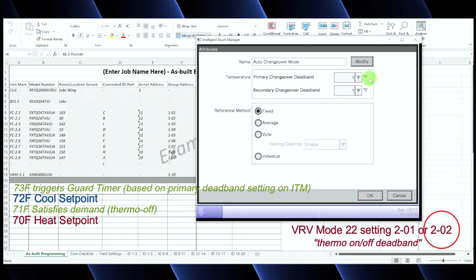You might have set it for 15. You might have left it at 60. I don't know. At any point in time, if the room temperature gets to this secondary deadband of 1 degree, so 74 degrees in our case, it will override the timer and immediately change over. I always leave the secondary changeover deadband at 1 degree. This is my safety. This is my, oops, it got too warm, or oops, it got too cold. I'm going to immediately override that guard timer and I'm going to change the mode.